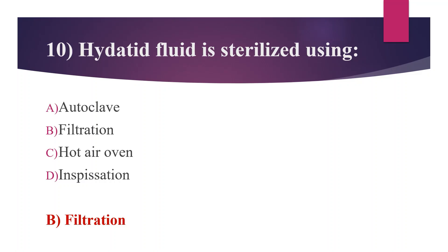Other options: In autoclave, the holding period is 121°C for 15 minutes at 15 psi. In hot air oven, the holding period is 160°C for 1 hour; it is used to sterilize glassware, forceps, scissors, scalpels, old glass syringes, swabs, and pharmaceutical products such as liquid paraffin, dusting powder, fats, and grease. Inspissation is used to sterilize LJ medium and Loeffler's serum slope, with sterilization at 80–85°C for 30 minutes on 3 successive days, using an instrument called an inspissator.